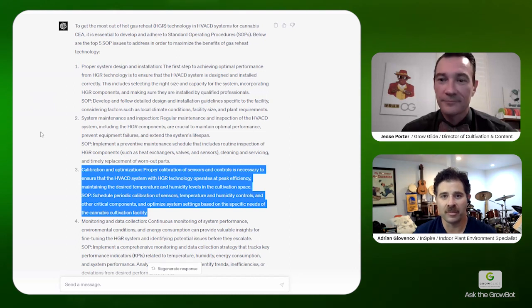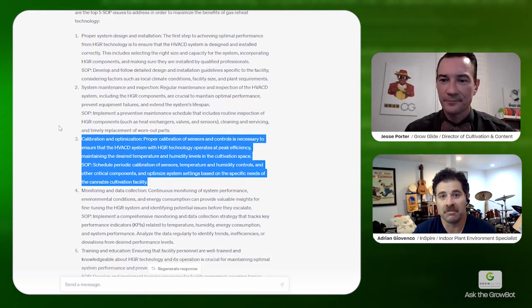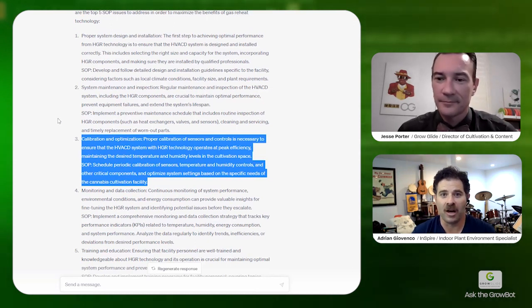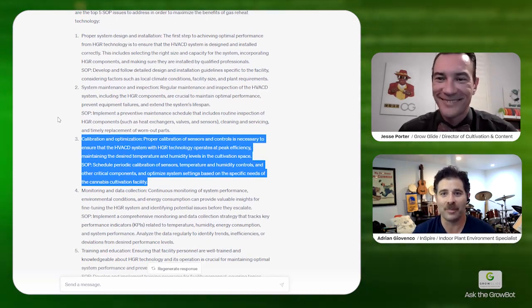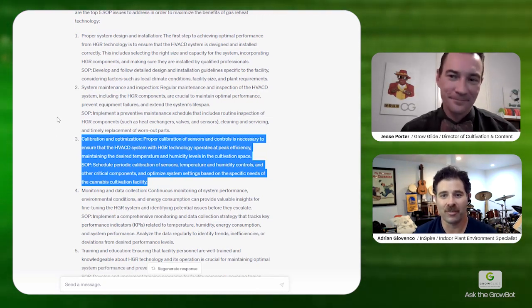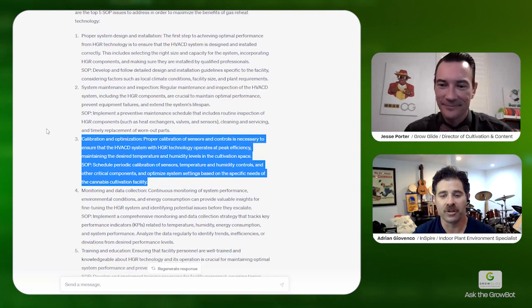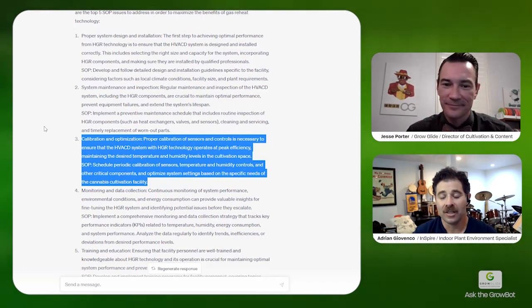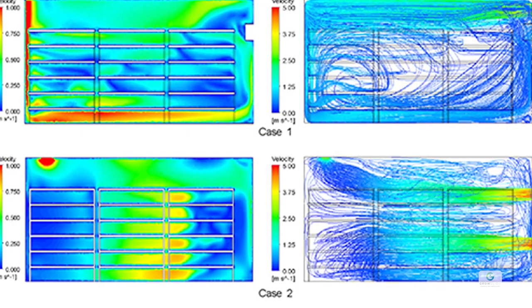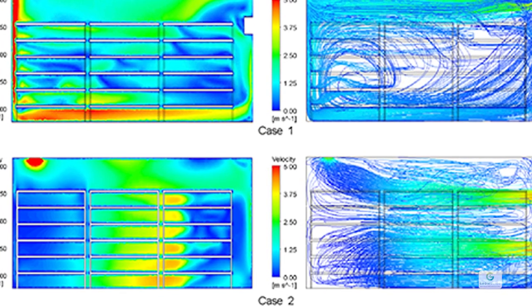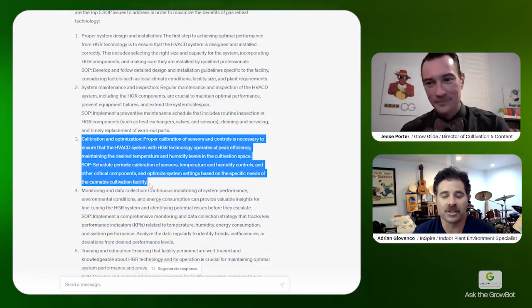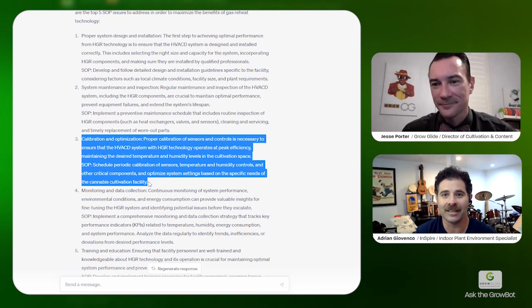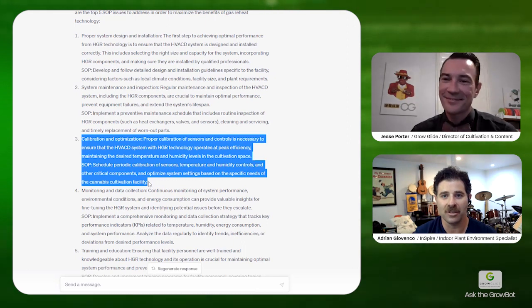I'm glad you brought that up because you're right. It's not super often, but there are times when they have the right capacity on both sides of the equation and everything, but they're still having those challenges. The first step is to benchmark it and see, are you really getting the capacity out of it? Back to airflow, if you're short circuiting your airflow from the supply to the return, it's not going to where the load is in the room. So you have the capacity, but you're just not getting that air mixed well down into where the load is and back to the unit.